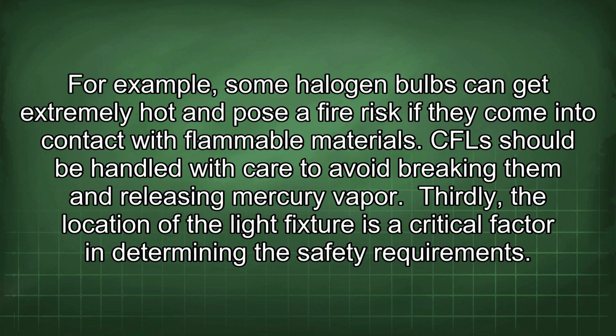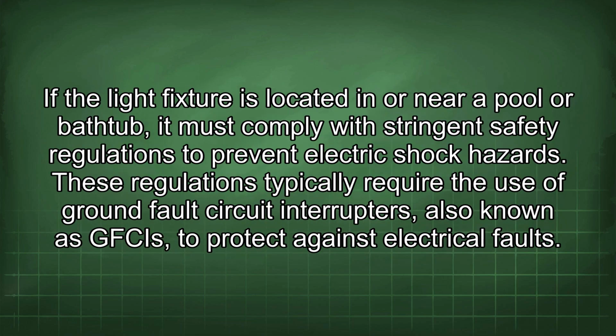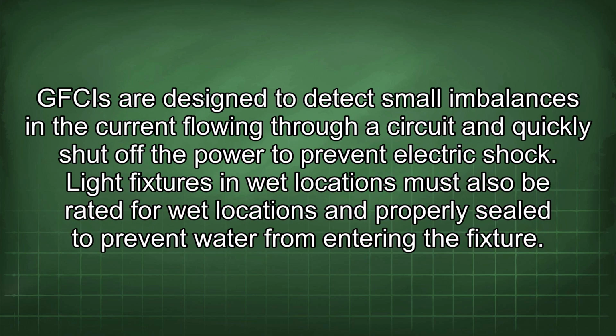Thirdly, the location of the light fixture is a critical factor in determining the safety requirements. If the light fixture is located in or near a pool or bathtub, it must comply with stringent safety regulations to prevent electric shock hazards. These regulations typically require the use of ground fault circuit interrupters, also known as GFCIs, to protect against electrical faults.